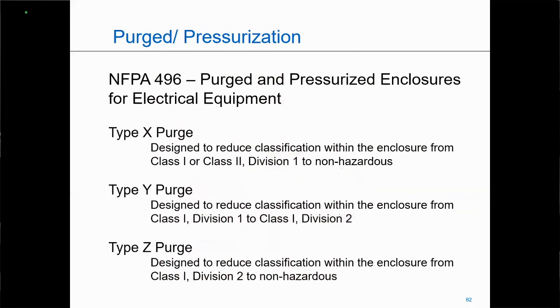So when I'm looking at purge and pressurized, I have my X, Y, and Z purges. The X purge is when I have a Class 1 Division 1 or Class 2 Division 1 area and non-hazardous equipment is inside. The X purge is required to be interlocked, so that if I lost my purge, automatically all the electrical equipment would shut down.